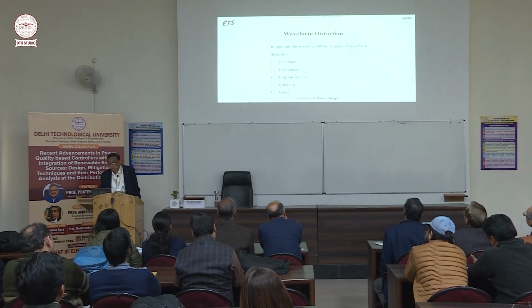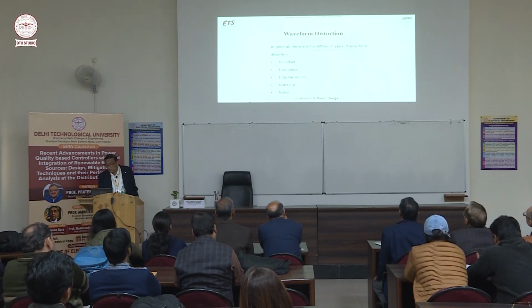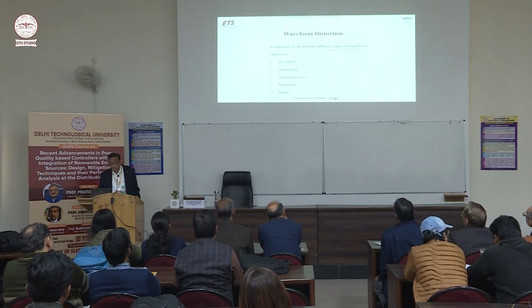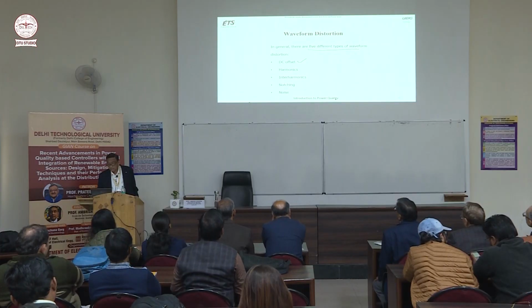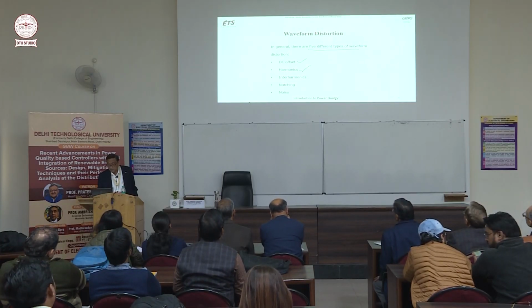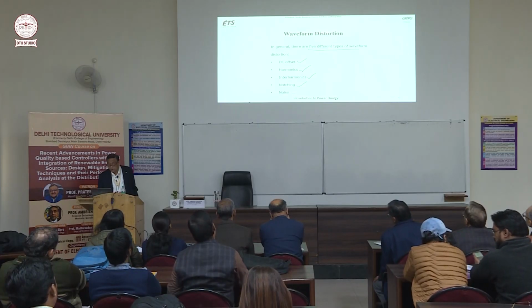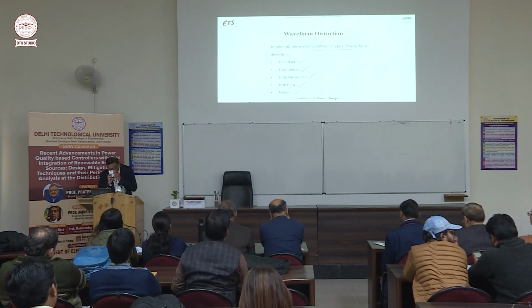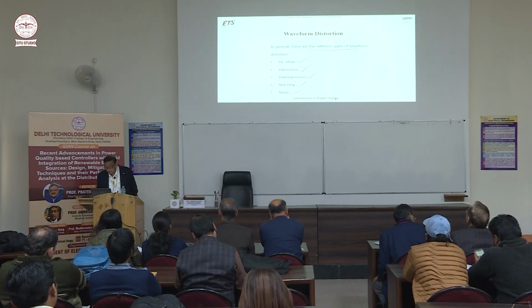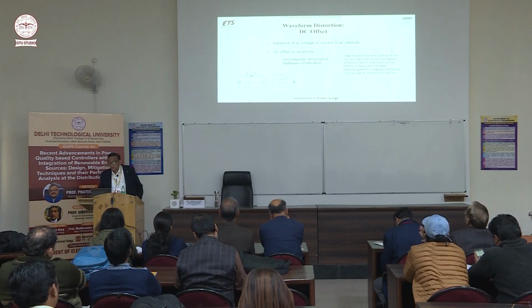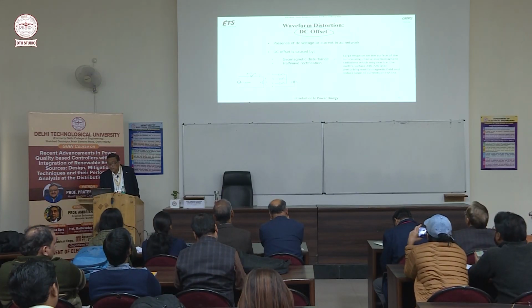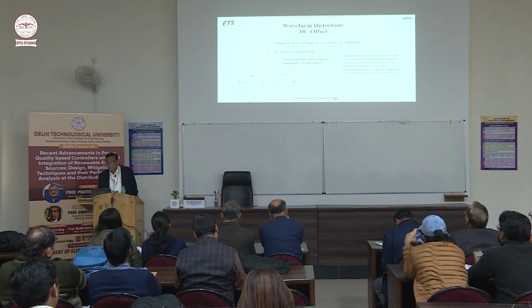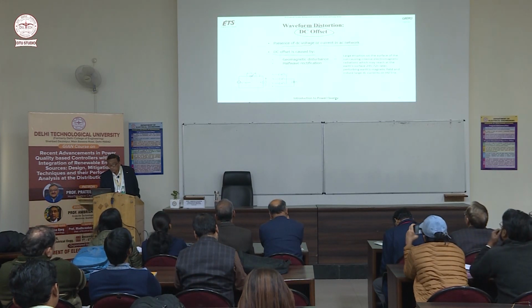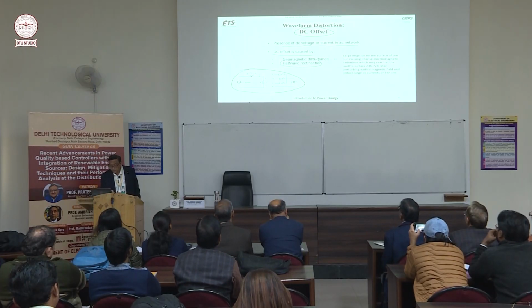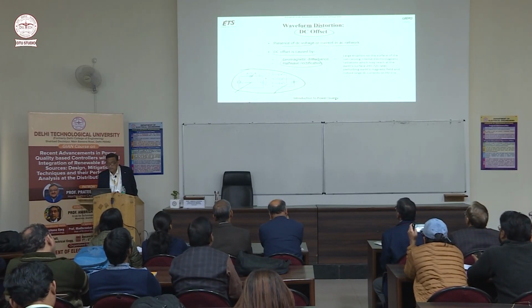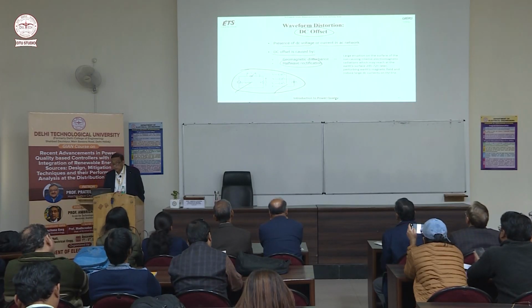Now the waveform distortion. There are 5 different types of waveform distortion. There may be DC offset, harmonics, interharmonics, notching and noise. Those are the 5 types of waveform distortion. Now DC offset is the presence of DC voltage or current in an AC network. DC offset is caused by half wave rectification. You already know the half wave for single phase or 3 phase. So this may cause DC offset.